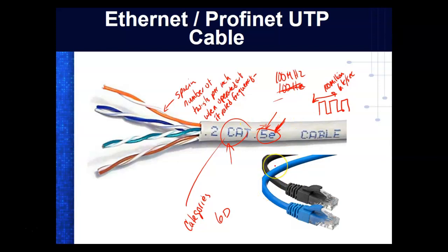That's actually what we're using to make our cables for our PLCs. There's a lot that determines this. We can't untwist these very far because we'll change the characteristic impedance, which is very important. So this right here is UTP, unshielded twisted pair. These would operate in PLCs or networks that are not in a very high environment where we have electromagnetic interference, or EMI. So this is what we're going to make because we're operating in a college. We don't have very much going on. And of course, shielded twisted pair is quite a bit more expensive.